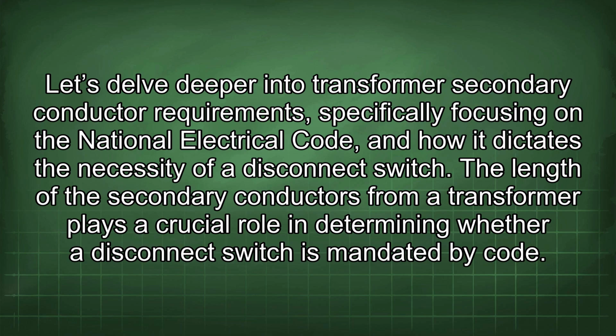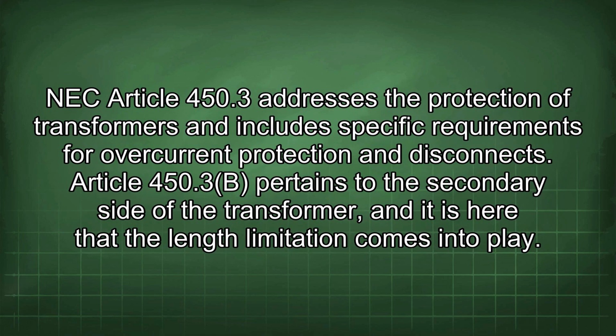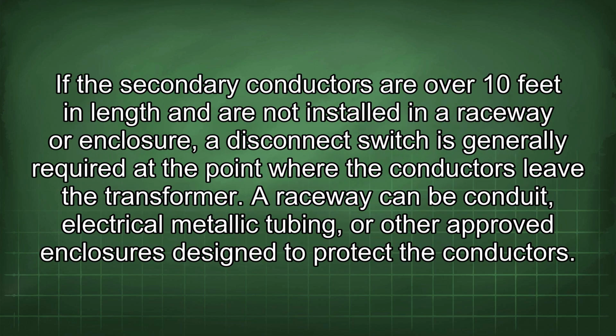The length of the secondary conductors from a transformer plays a crucial role in determining whether a disconnect switch is mandated by code. NEC Article 450.3 addresses the protection of transformers and includes specific requirements for overcurrent protection and disconnect. Article 450.3(B) pertains to the secondary side of the transformer, and it is here that the length limitation comes into play. If the secondary conductors are over 10 feet in length and are not installed in a raceway or enclosure, a disconnect switch is generally required at the point where the conductors leave the transformer.